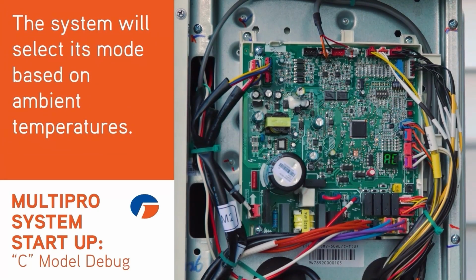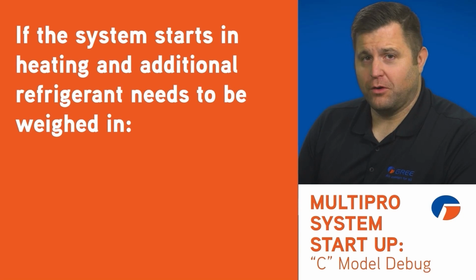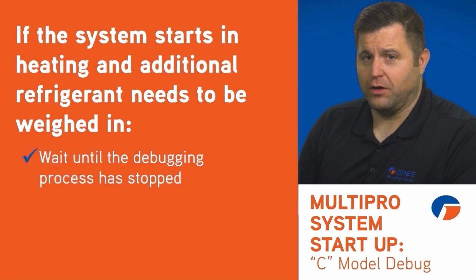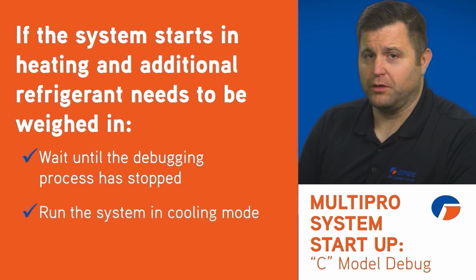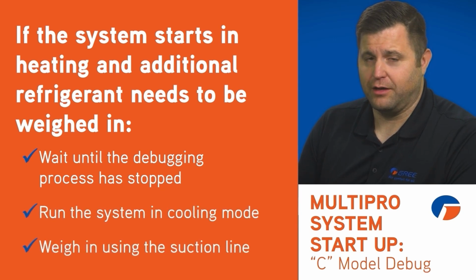The system chooses heating or cooling automatically based on ambient temperatures. If the system is starting in heating and you need to weigh in additional refrigerant, you'll wait until the debugging process is stopped, run the system in cooling, and then weigh in using the suction line. The system will run for 45 minutes to an hour.